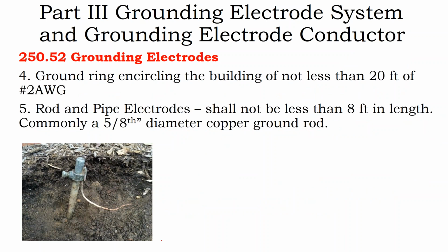So what's generally common is that you have a ground rod going into the ground. But one problem with ground rods is that they have to be driven 8 feet into the ground, and that can be a difficult task in many areas. And so there's other ways to build grounding electrodes, but if you can drive a ground rod 8 feet into the ground, then that's the best way to do it. If you're using a ground rod or a ground pipe, often you'll get more leeway in the size of your equipment ground conductor than you would where you're making your own grounding electrode out of bare copper wire by digging a trench and burying it directly into the ground. You can, or you're taking a bunch of bare copper and throwing it into the foundation of your house.